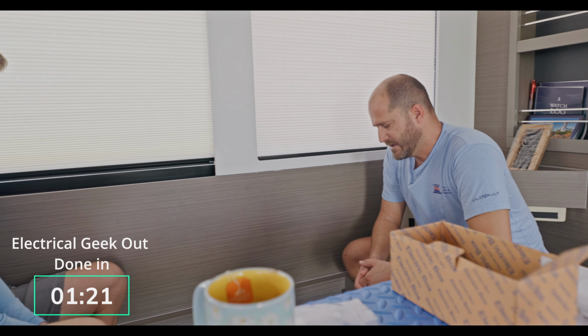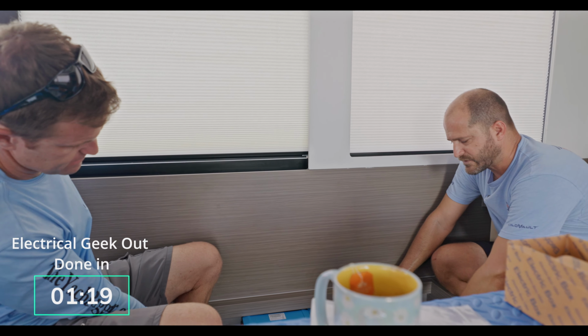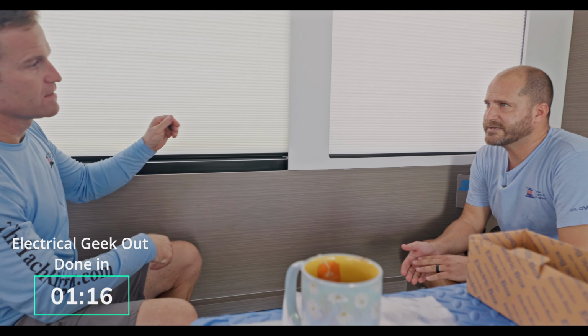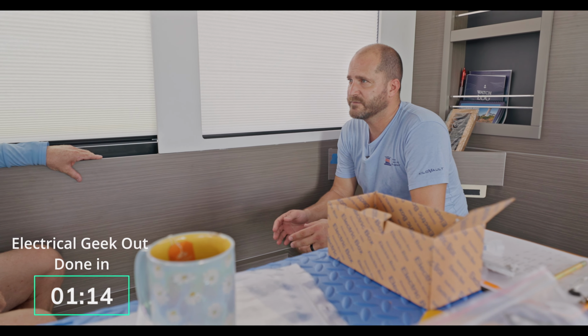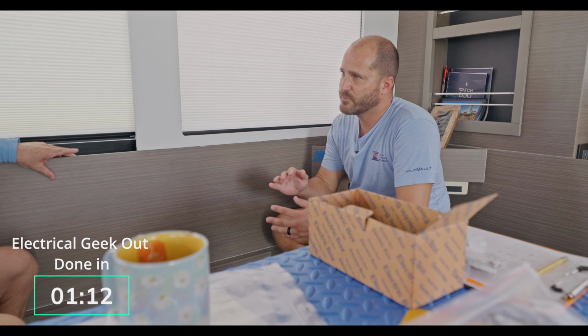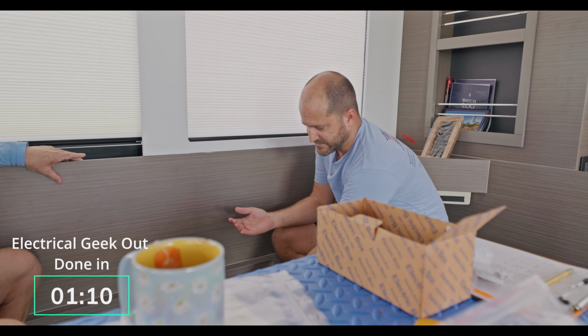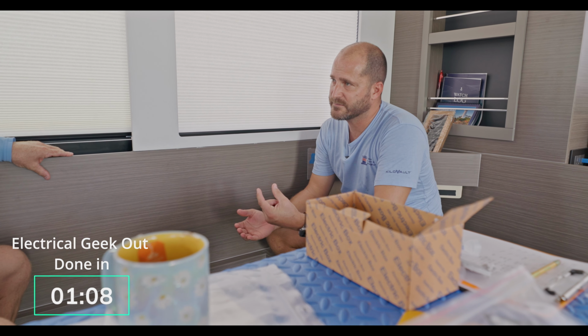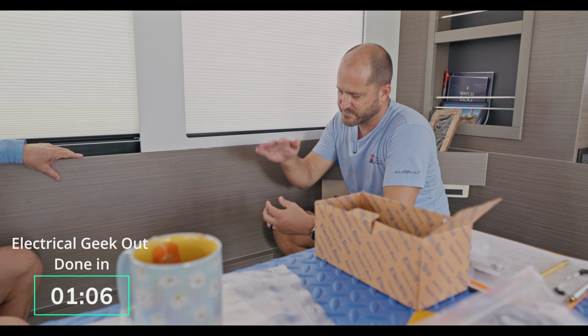So Class T fuses are for pure safety. And the reason for the Class T fuse is the AIC, the amperage interrupt current. A fuse has a lot of different ratings. Of course, let's say that's a 400 amp Class C fuse, it's designed to open at 400 amps, not quite — there's a bit of a chart.